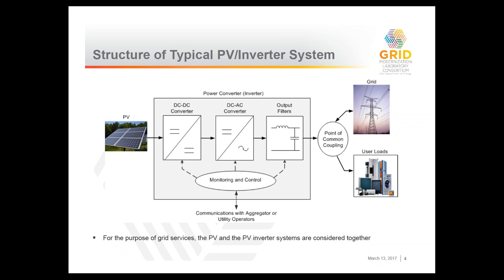So this particular one has a DC to DC converter followed by a DC to AC converter, which is called an inverter, and then an output filter, and then it connects to the grid, and it can also supply some local loads. There are different varieties. For example, there can be a single stage, which means there is only one converter, or there can be a transformer at the output, or there can be a transformer at the DC to DC converter.